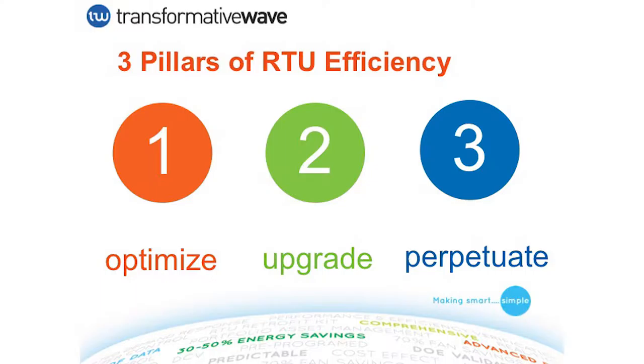We call this recommissioning, or tune-up programs—getting back to factory level performance: clean coils, optimized airflow, correct refrigerant charge. You want to restore the machine to the best day it ever had leaving the factory, which is an ongoing challenge in its own right.